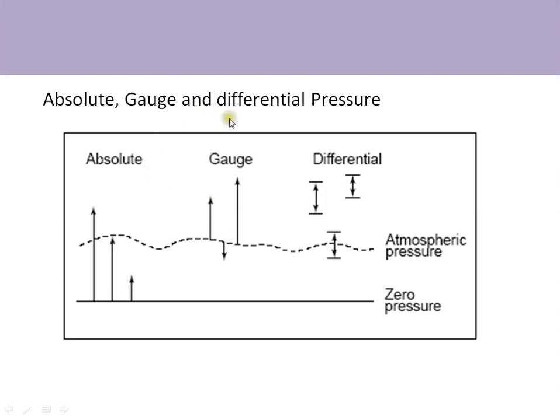This is the classification of pressure: absolute pressure, gauge pressure, and differential pressure. Absolute pressure is always specified with respect to zero, and vacuum is generally specified in absolute pressure. For example, if you specify a vacuum value as 10⁻² millibar, it is always with respect to zero. Gauge pressure is specified with respect to the atmosphere — for example, 10 psi(g) means 10 psi above the atmosphere.